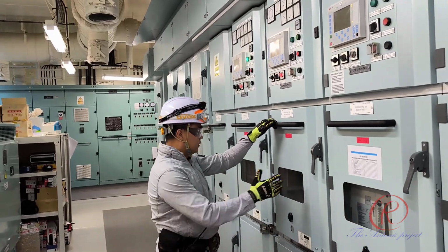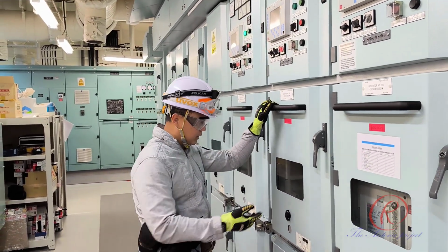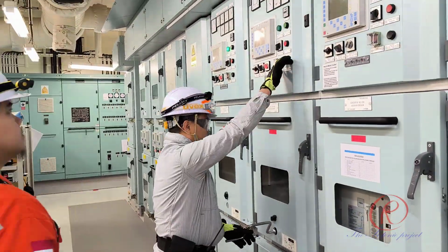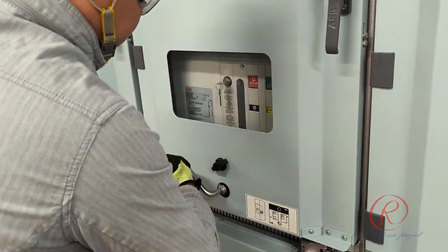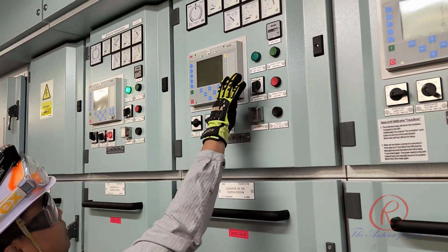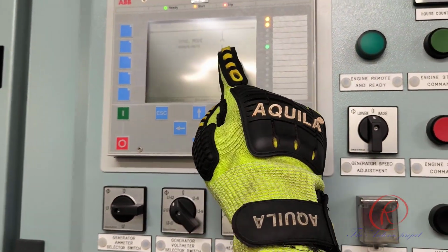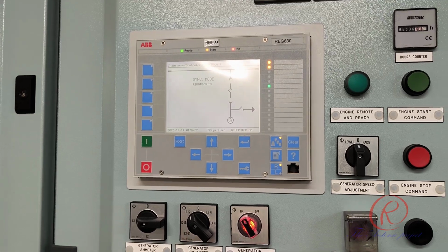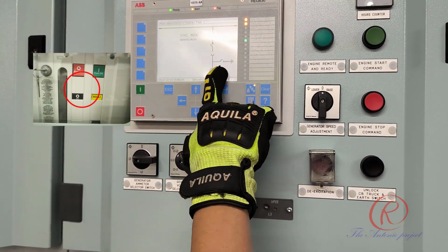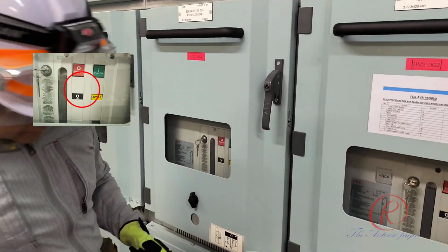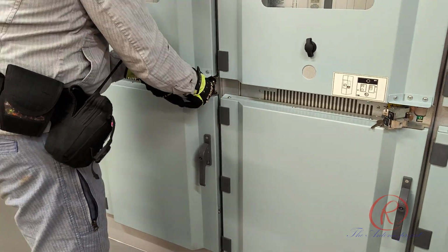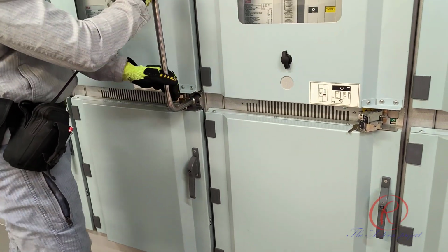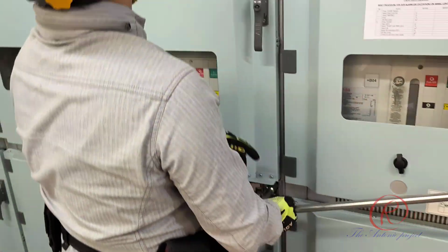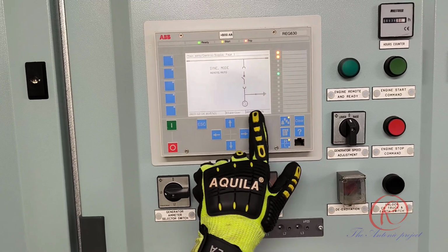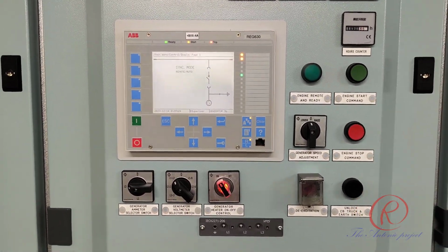Preparation of the alternator maintenance. At first, the VCB or PCB is necessary to be racked out. From the HMI monitor, confirm that the PCB or VCB circuit breaker is in open position. Also confirm the PCB indicates 0 or open. Next is to close the earthing to discharge leftover electric energy from the electrical line. The grounding connected to the line is checked on the mimic diagram in the monitor.